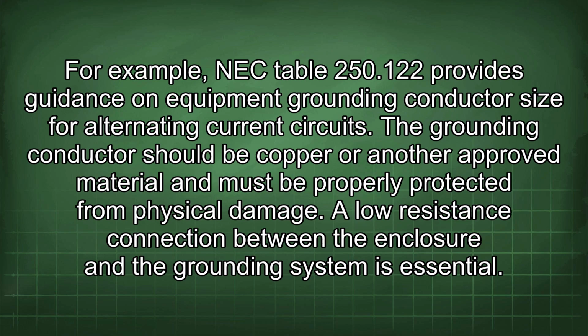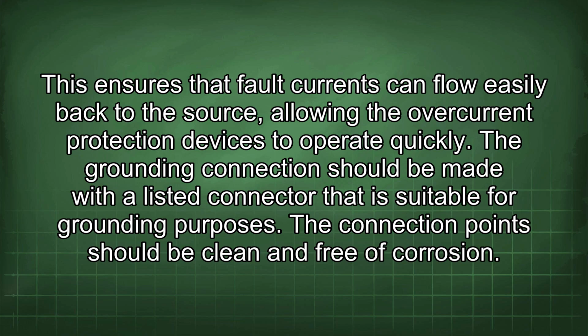A low resistance connection between the enclosure and the grounding system is essential. This ensures that fault currents can flow easily back to the source, allowing the overcurrent protection devices to operate quickly. The grounding connection should be made with a listed connector that is suitable for grounding purposes. The connection point should be clean and free of corrosion.